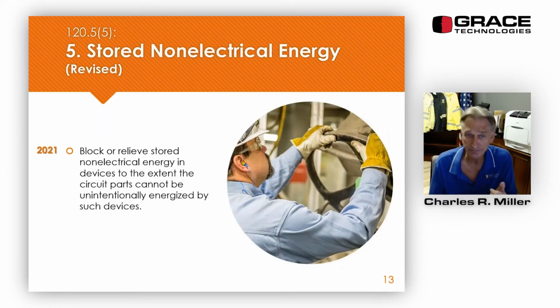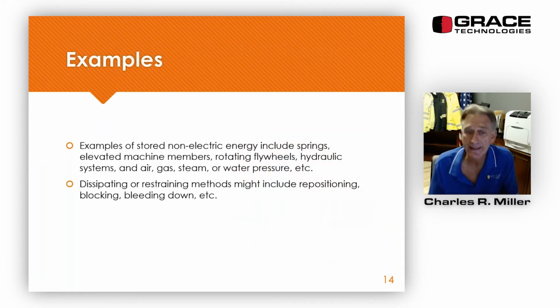All right, number 5. As I mentioned a few minutes ago, it's stored non-electrical energy, and in 2021 it was changed from stored mechanical energy to non-electrical. Block or release stored non-electrical energy in devices so that the circuit parts cannot be unintentionally energized by such devices. Some examples would be springs, elevated machine members, rotating flywheels, hydraulic systems, air, gas, steam, water pressure, etc. Well, how are we going to dissipate these?